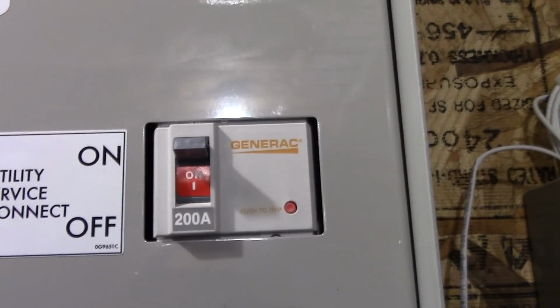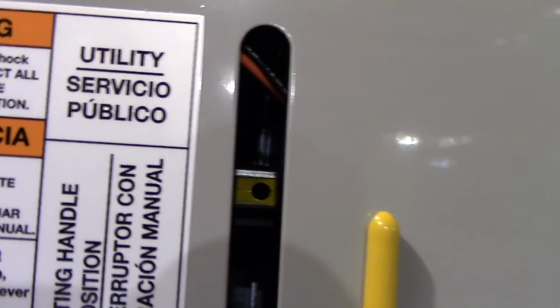So here's the utility service disconnect, 200 amps, and there's the transfer switch right there. You see that little brass looking thing with the hole? That's the switch itself, and this little tool taped on the side here is a lever you can put in there to make the transfer switch go between utility, as you can see right there, or generator.